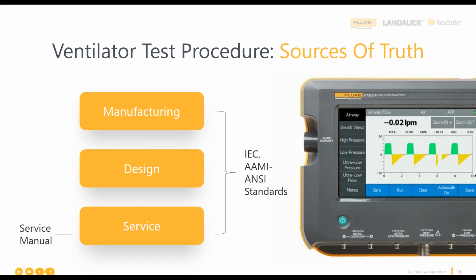The number of test points, test settings that need to be evaluated may be more or fewer, depending on which part of the process that you're in. They may need to be repeated because you find that what you thought was going to work maybe doesn't work quite the way that you intended it to. And in manufacturing, as we said before, it's the first time that all of the pieces parts have been put together into a complete medical device that can and must then be tested to make sure that it's safe and effective before it ships out to the customer or the end user. Biomeds, you all know how important it is to carry out the testing on a scheduled maintenance or periodic basis. And as we said before, in terms of the ventilator, it may be based on the use hours of that ventilator and not just on a calendar periodicity.